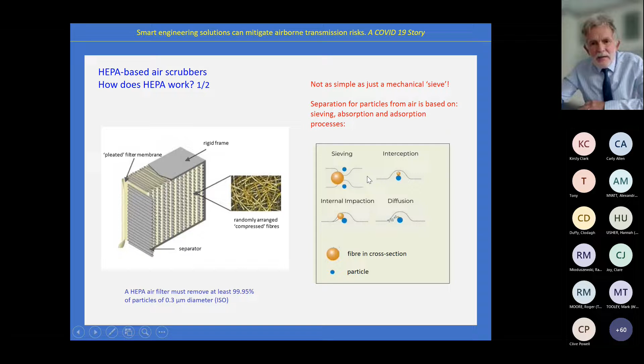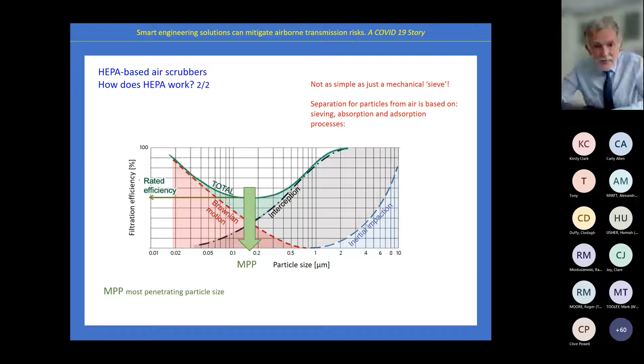What we have, as particles get smaller, you start to get reaction with the particles, with the fibers. And we call these, if you like, a combination of absorption processes, and I won't go into them in any detail. Chris gave us this diagram. If you put all those forces together plus mechanical sieving, you get a performance which has a minimum, and the minimum performance defines what it says on the tin, i.e. what its particle size is. Smaller particles will be held up in the filter far smaller than its MPP, its most penetrating particle size specification. So Chris's very, very small particles will be very highly retained by a HEPA filter, even though it's specified as having a cutoff of, shall we say, 0.2 microns. It'll work far less than that. Okay, so viruses, small viruses, if they were singletons, will be held up by this.